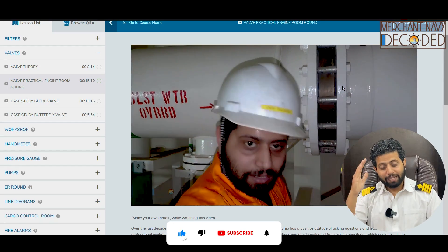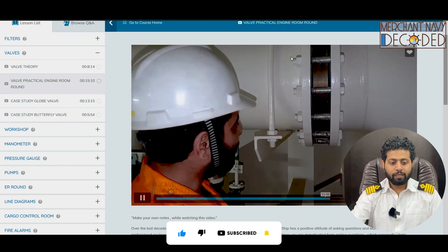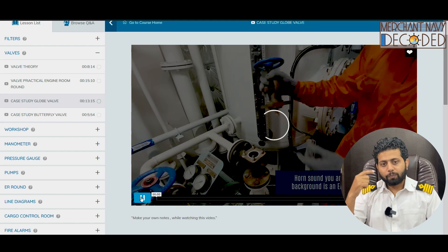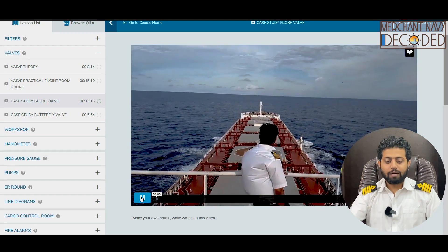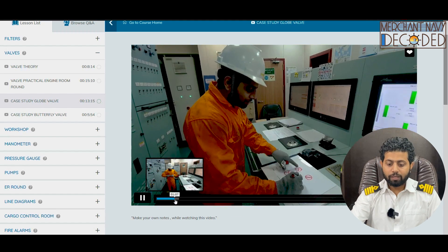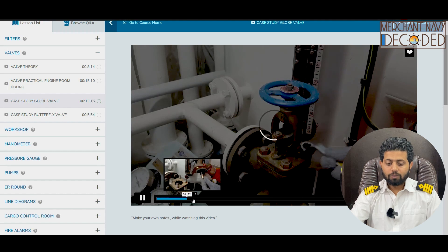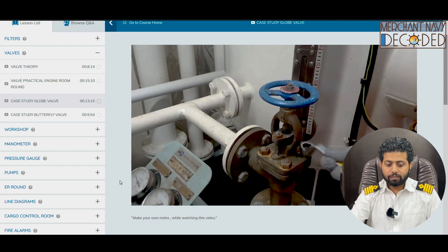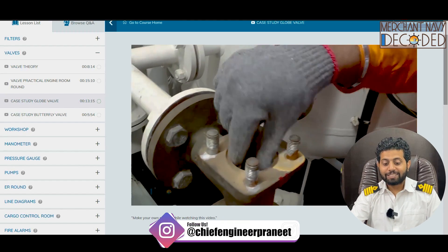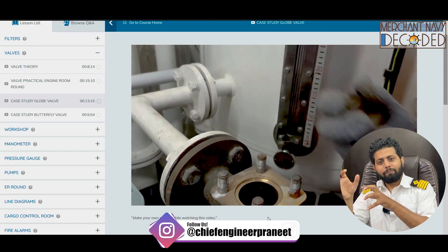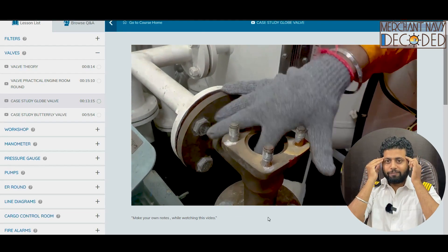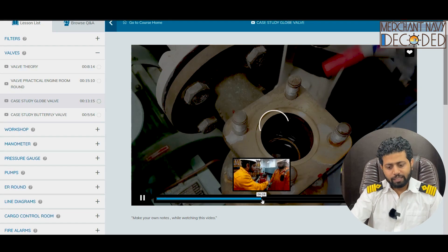A lot of animation has been involved, it will surely help you in understanding. Then there is a case study of a globe valve. As a chief engineer, I've got my fitter along with me and we are discussing what all problems you can face while overhauling a globe valve — why does a globe valve get damaged and what all precautions you need to take care of. I am overhauling a globe valve, discussing how you can make out just by looking at the valve whether it's a non-return globe valve or not. We are opening up a non-return valve to check the internals — this non-return valve does not have a valve disc attached to the spindle. The theory part and the practical part are all linked together.